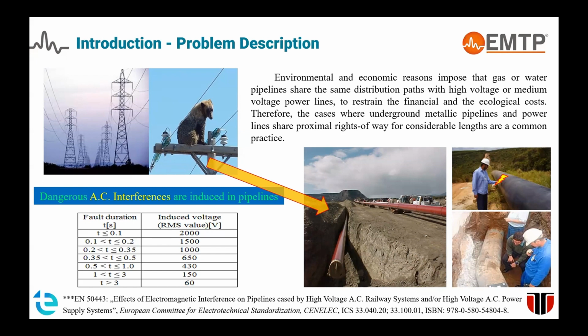The standards and regulations impose some limits with regard to the maximum level of the induced voltage that is allowed to appear in such metallic structures. We have here some imposed values with regard to the time duration of the effect of the fault, from a point of view of safety of the person who could come in contact with the metallic structure. From a point of view of corrosion, the induced voltage level should not exceed 1.2 volts. So from a corrosion point of view, these limits are more drastic.